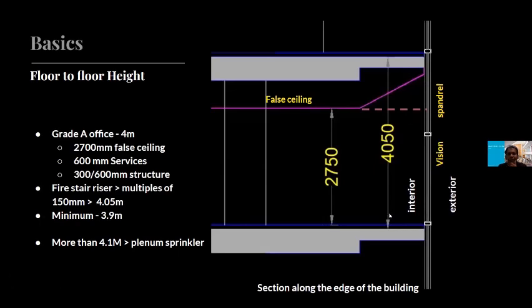The floor to floor height is decided by: you need 9 feet clear space within the office, that's 2.7 meters. Then another 0.6 meters for the ducts, HVAC, AC ducts, and so on. And another 2 feet, 600 millimeters, for the structure. That brings you to this number.